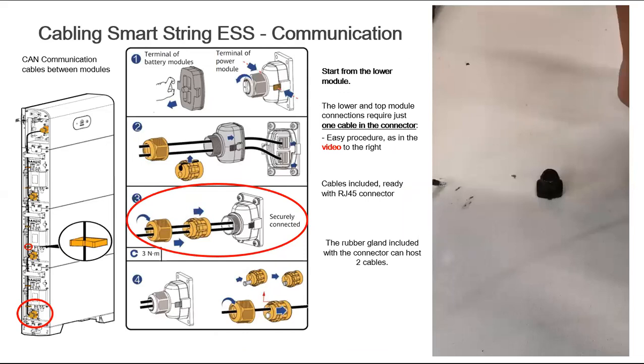Communication cable. We are also providing the communication cables between the battery modules and the power control modules inside the boxes. So again, you don't need to make the cables yourself. You just take out the cables and easily connect them between the power control modules and the battery modules. The RJ45 connectors are also crimped. So you just need to make sure that you first pass the cable through the locking nut, and then connect the cables to the RJ45 connectors inside the power control module and battery modules.